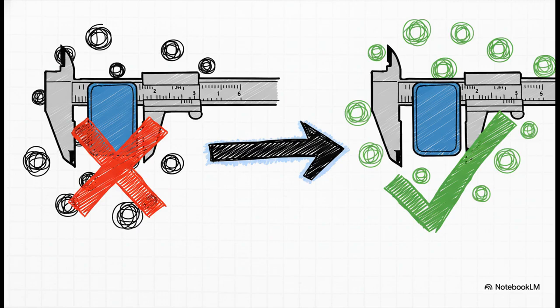To get proof you can rely on, your tests have to be reliable too. This is something called test method validation. You literally have to prove that your measurement equipment and your test procedures are accurate and consistent. I mean, if your test for measuring a catheter's diameter gives you a different number every time you run it, that test is totally useless, right?